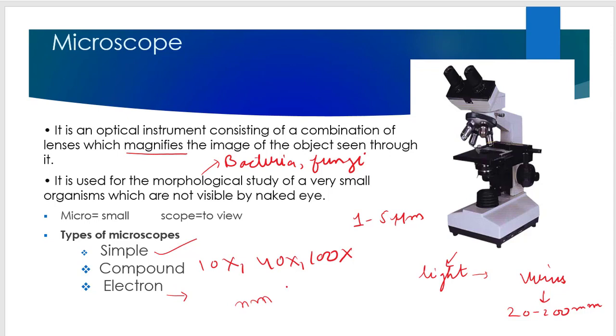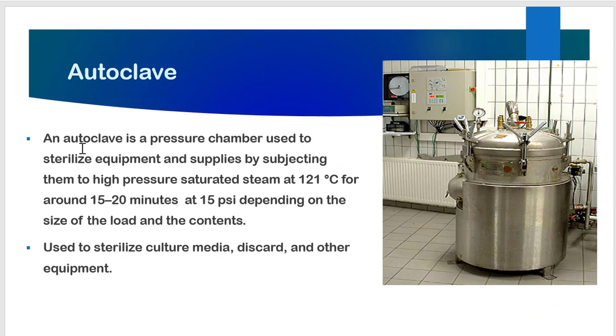The electron microscope consists of electrons instead of light, so it magnifies things to the nano range. It includes the scanning electron microscope. Moving ahead to the next equipment, we have the autoclave. The autoclave is a pressure chamber used to sterilize equipment and supplies by subjecting them to high-pressure saturated steam at 121 degrees Celsius for around 15 to 20 minutes at 15 psi — pounds per square inch — depending on the size and load of the contents.